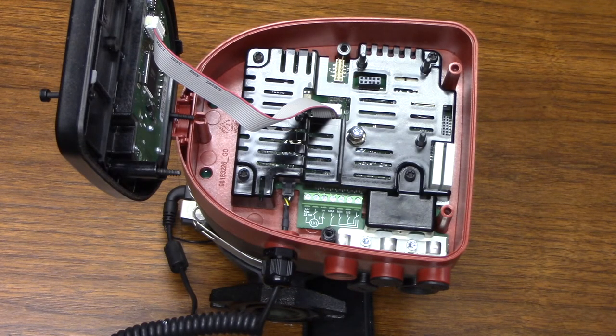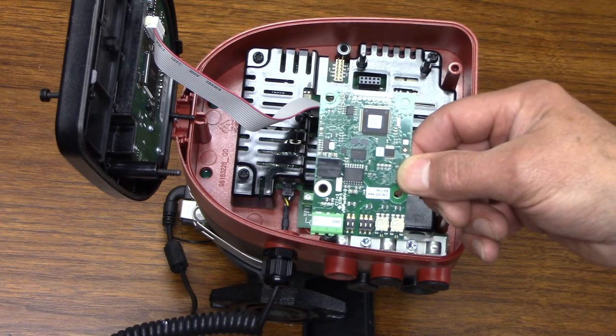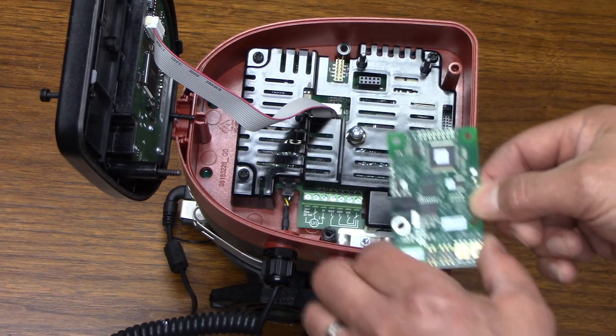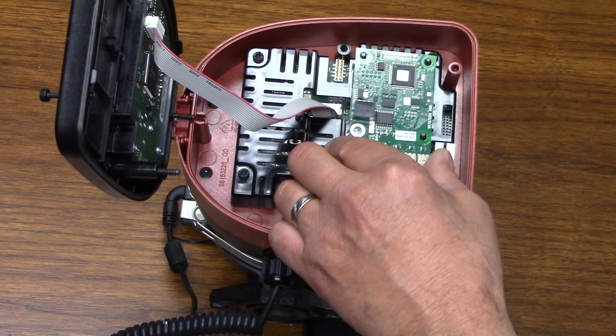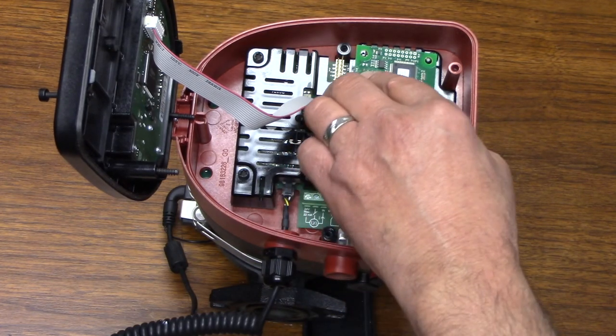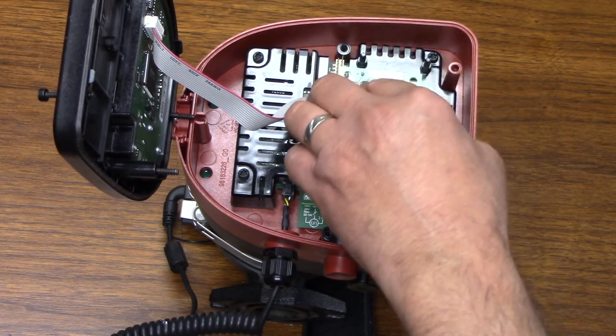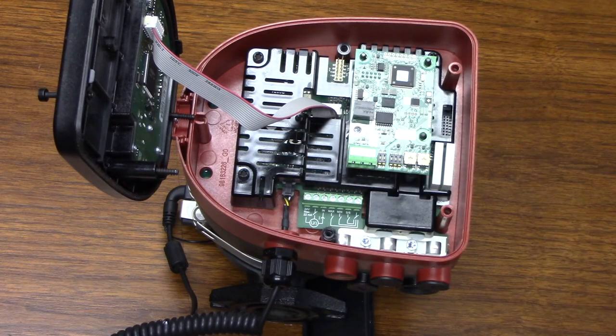The last is the communication interface module. That is an optional device that goes internally to the unit, and you get to play with four different types of communication protocols: BACnet, LONWORKS, Modbus, or Profibus.